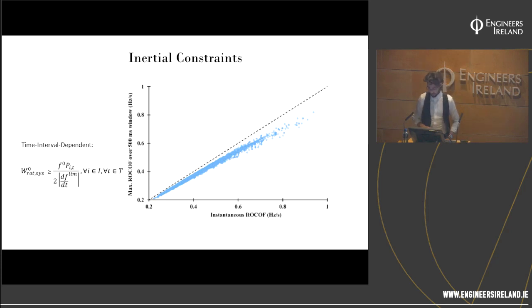Every power plant or protection device will be reading the frequency. They have to measure the frequency from the grid to know that, oh God, the rate of change of frequency is above a certain threshold. Okay? And that's done over a certain window. If anybody ever talks about rate of change of frequency, the question you ask back is over what time frame, okay? Because it doesn't mean anything unless it's over a certain time frame.